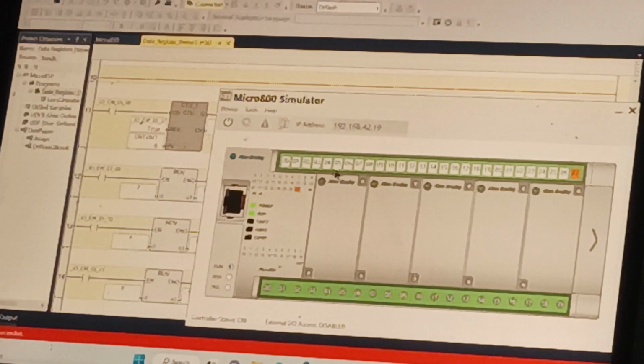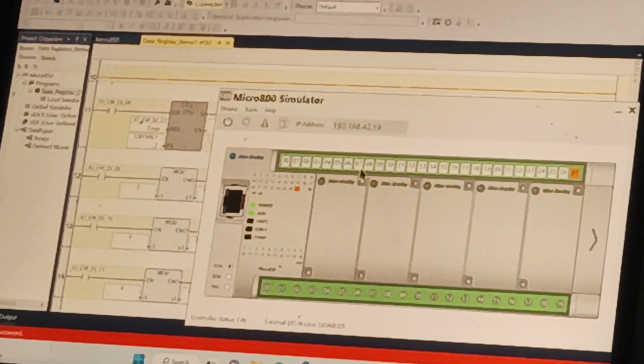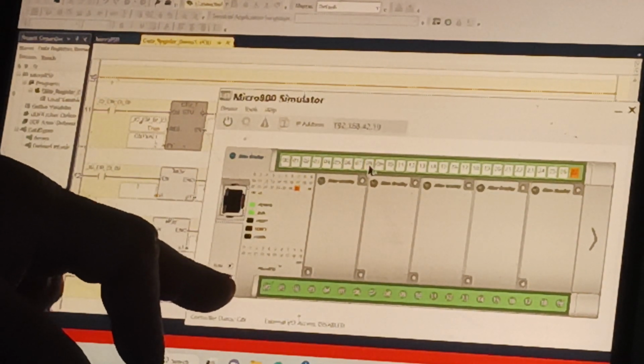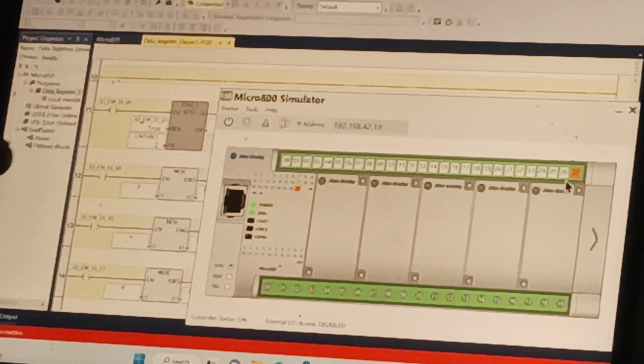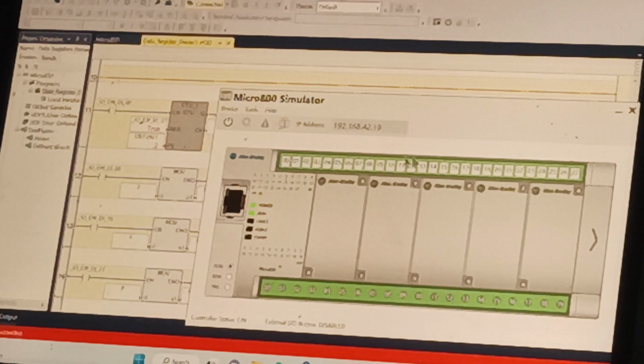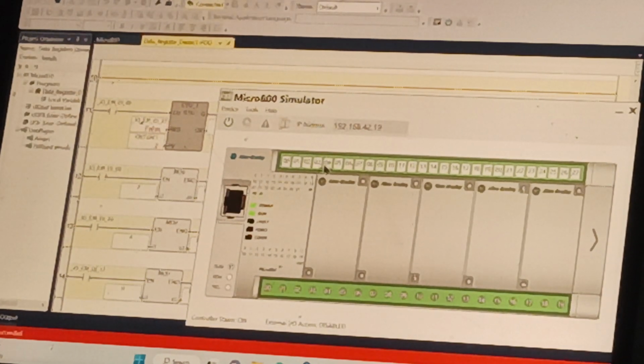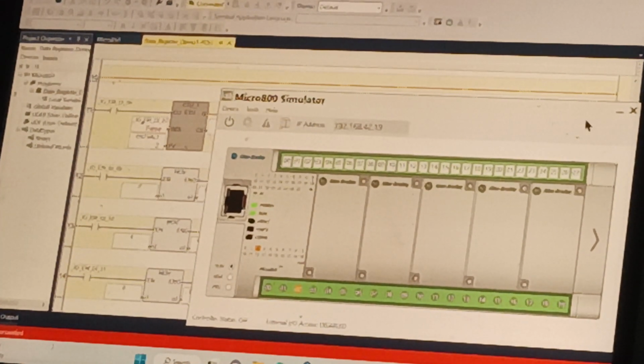So I'll press input 9, and we'll set our count value to 2. Then rather than pressing it 6 times, I just have to press input 8 2 times. 1, 2. And, oh, you know what? I left my reset on. Oops. So that's why it wasn't doing anything. That's why you want your reset to be a push button too, so you don't toggle it on and leave it on and things get jacked up. So now my move value is still 2, and I'm going to try this again. 1, 2, and our counter just turned our output on.